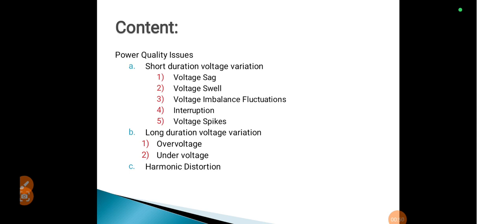Then we are going to see the different power quality issues. According to their duration of occurrence, there are mainly two types of power quality issues: short duration and long duration. Short duration includes voltage sag, voltage swell, voltage imbalance, interruption, and voltage spikes. Long duration includes under voltage and over voltage. And the last one is harmonic distortion.